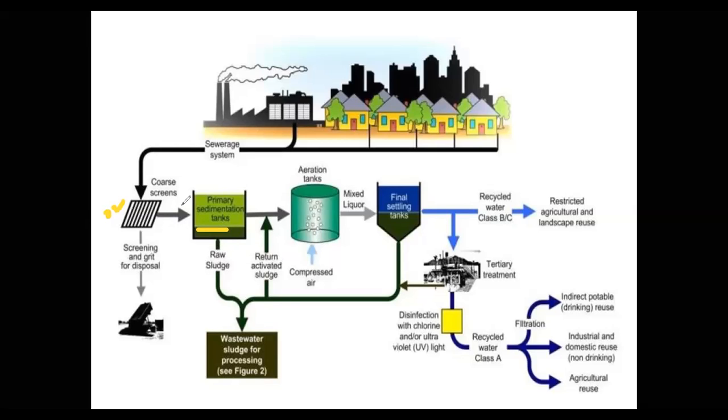Otherwise you will think that you are treating water or wastewater only. You should not ignore the solid waste generated during the treatment process. Equally, you should concentrate on the solids which are going to be generated in the sewage treatment plant. Now, in the primary sedimentation tank, what is happening? The settleable solids settle down at the bottom by gravity, and we call that sludge, and then it will be sent towards the treatment process.